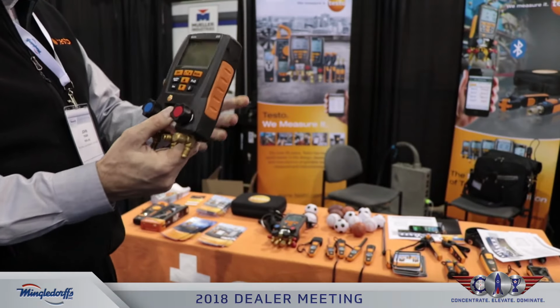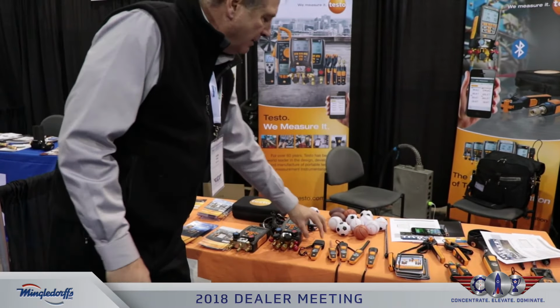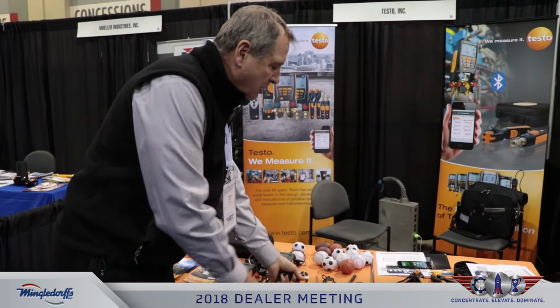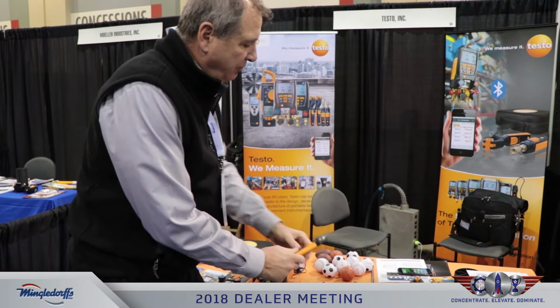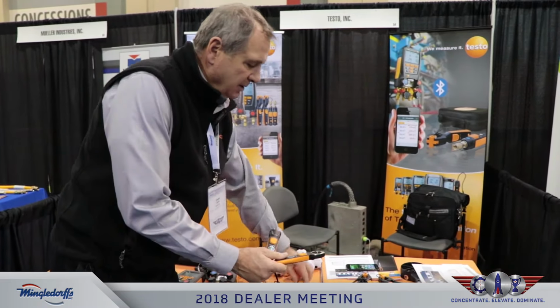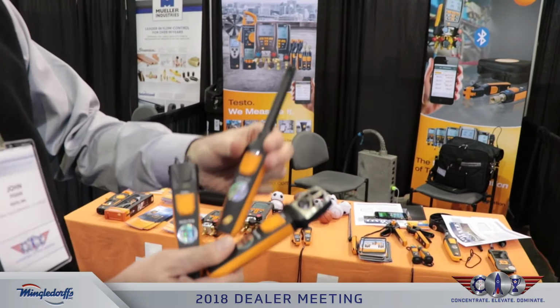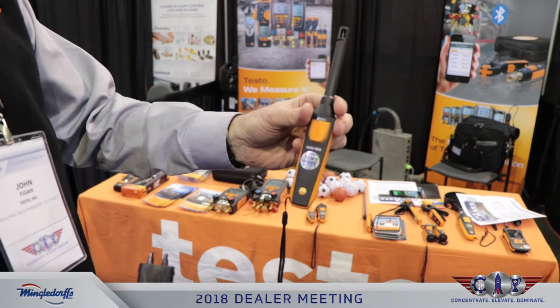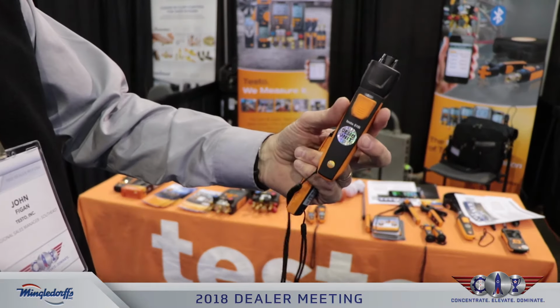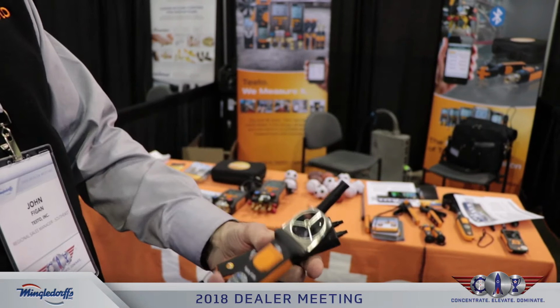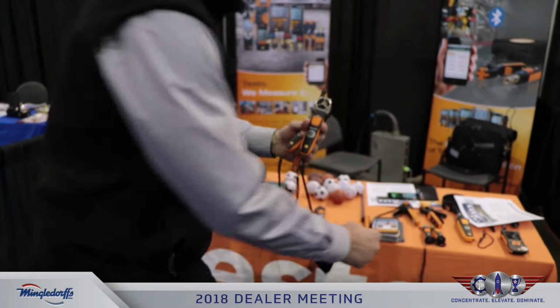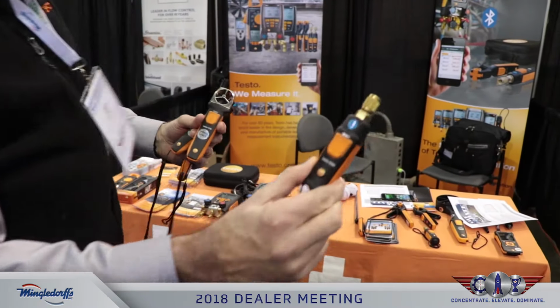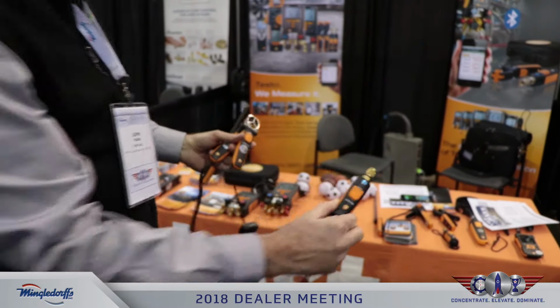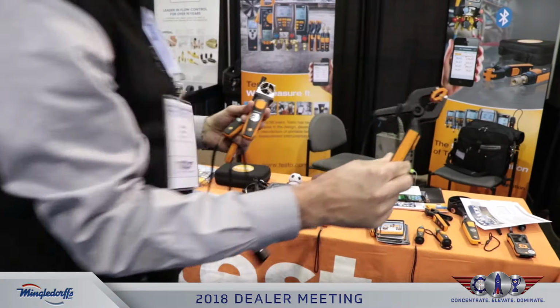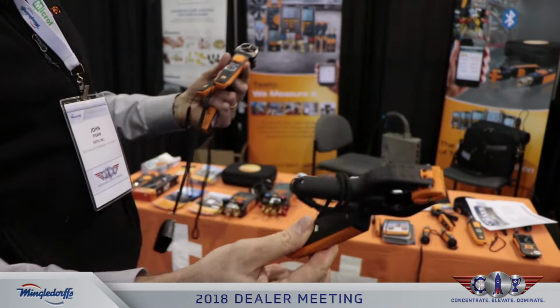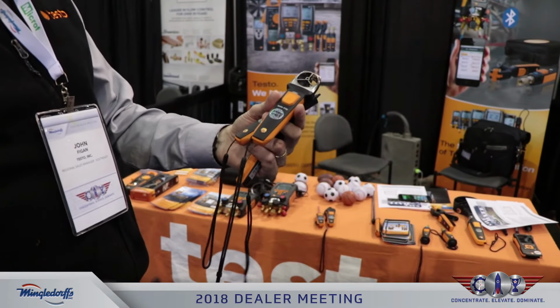In addition to the gauges, we have a full line of smart probes, we call them. Each one of these probes can measure something different. Like for instance, this one measures relative humidity, temperature, and wet bulb. This could measure differential pressure or static pressure. This measures airflow, refrigeration pressure, and a pipe clamp probe. So there's a family of roughly around 12 of these.